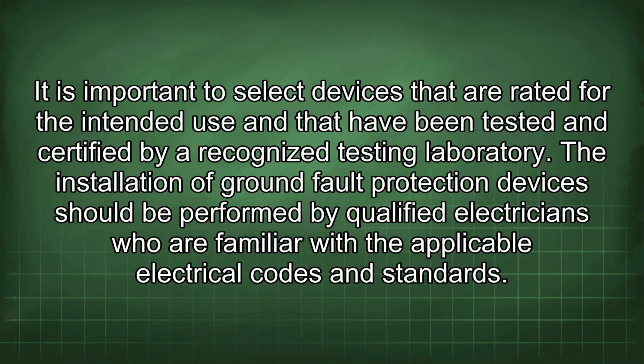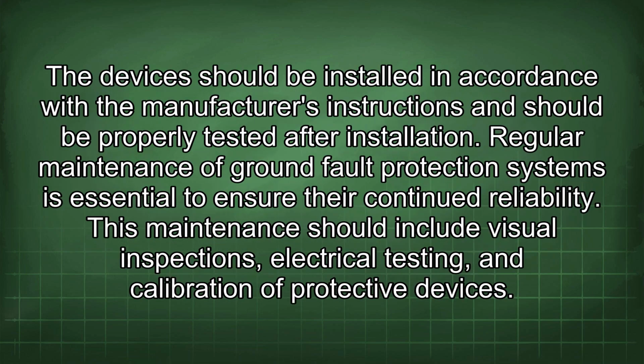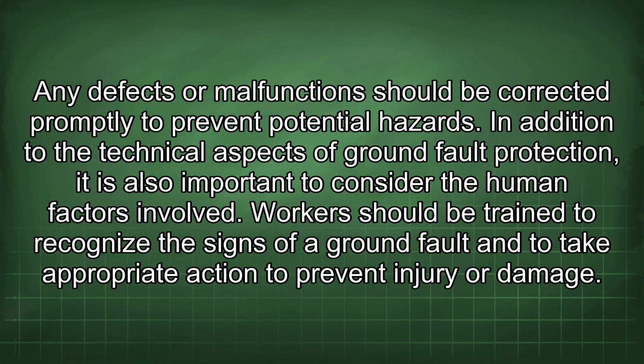It is important to select devices that are rated for the intended use and that have been tested and certified by a recognized testing laboratory. The installation of ground fault protection devices should be performed by qualified electricians who are familiar with the applicable electrical codes and standards. The devices should be installed in accordance with the manufacturer's instructions and should be properly tested after installation. Regular maintenance of ground fault protection systems is essential to ensure their continued reliability. This maintenance should include visual inspections, electrical testing, and calibration of protective devices. Any defects or malfunctions should be corrected promptly to prevent potential hazards.